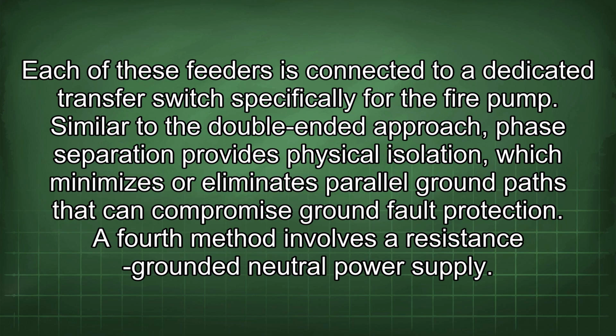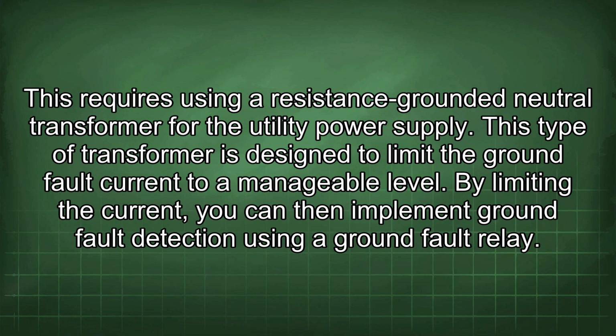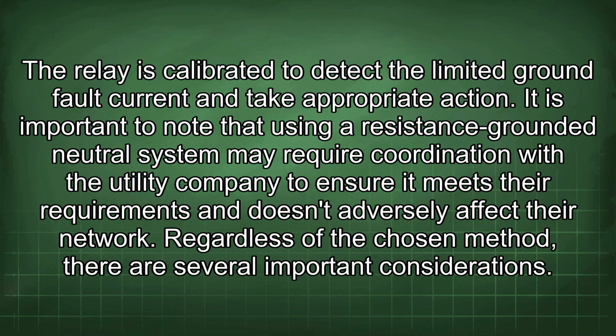A fourth method involves a resistance-grounded neutral power supply. This requires using a resistance-grounded neutral transformer for the utility power supply. This type of transformer is designed to limit the ground fault current to a manageable level. By limiting the current, you can then implement ground fault detection using a ground fault relay. The relay is calibrated to detect the limited ground fault current and take appropriate action.